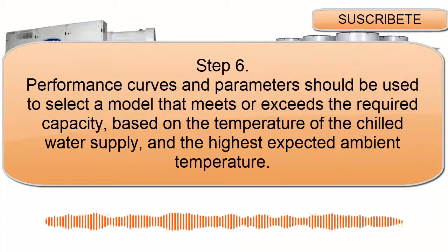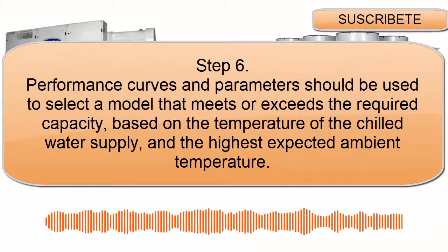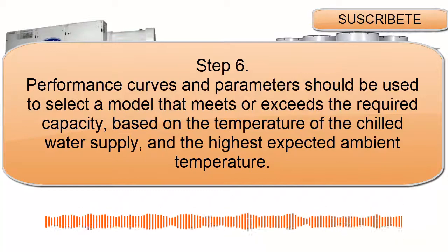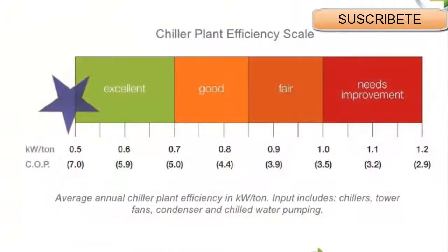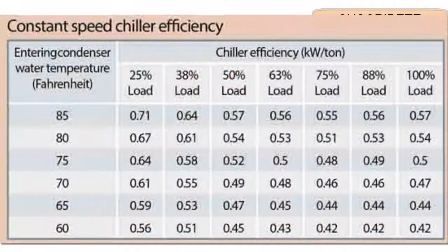Step 6: Performance curves and parameters should be used to select a model that meets or exceeds the required capacity, based on the temperature of the chilled water supply and the highest expected ambient temperature. The margin of safety of the application must be considered with respect to the sizes of coolers available.